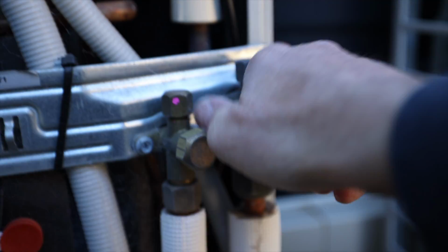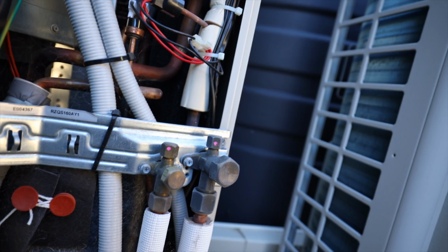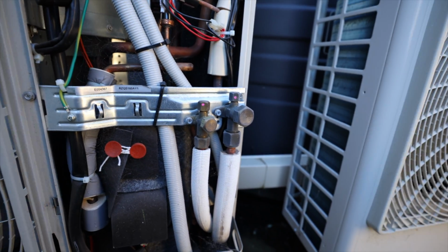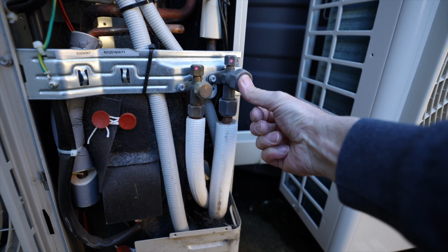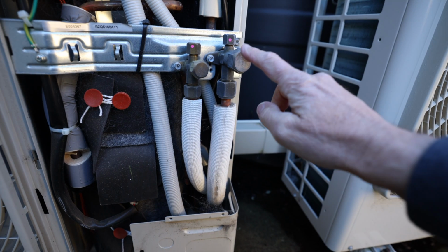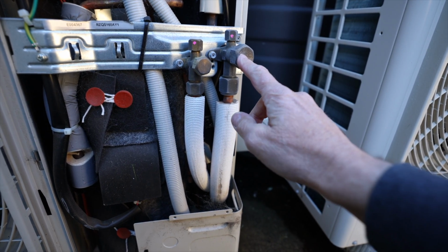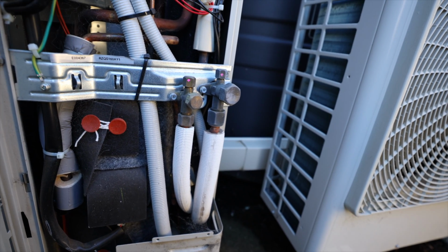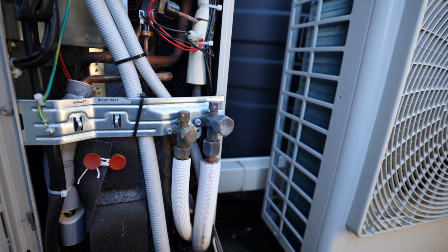Coming back on this pipe here, which is our gas pipe. In heating, we're sending the hot gas in. At the moment, that is freezing cold. So if I wet my finger and stick it there, it's actually freezing my finger. So that's minus 37 degrees. Stick your tongue on that one and you're sure to lose a fair bit of skin off the tip of your tongue. Wouldn't recommend it.